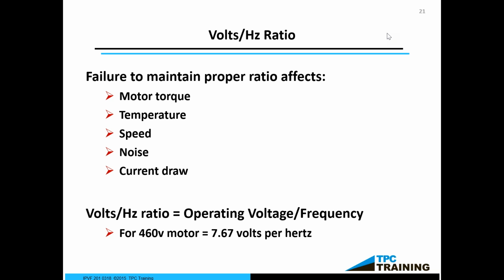Okay. Next question, Joe. When you said every 1 horsepower is 3 foot-pounds of torque, is that only during start to speed up, or is that continuous? Each motor has its own torque. It's 3 foot-pounds of torque. Each motor has a NEMA design to it, whether it be NEMA A, B, C, or D. If you look at the nameplate, each motor has a NEMA design code on it. So it's 3 foot-pounds of torque, no question about that, but each motor is unique in its particular torque curve. Whether it's starting torque, running torque, or accelerating torque, that's all based on their particular torque curve.